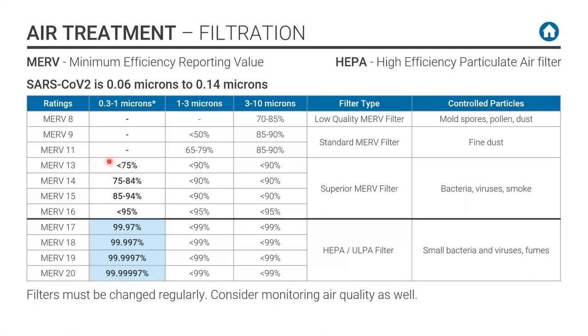So we're recommending, and ASHRAE is recommending, a minimum of 13. We'd like to see a 14. We don't think it's a heavy lift from a pressure drop to go from a 13 to 14. It does have a minimum capture rate. HEPA filters, the high efficiency particulate filters, are used in hospitals, and those are the ones in blue here.